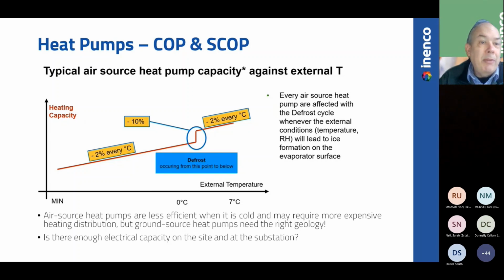The big issue with heat pumps is that air source heat pumps are less efficient and have less capacity when it's cold, and they require a defrost cycle, which may mean they need thermal buffers. Ground source heat pumps are much better, but they rely on the underground geology being suitable - you need flowing water or other permeability conditions, and we think very few sites have that. Heat pumps also tend to produce water at about 45-50 Celsius, meaning you need new radiators and pipes, and these are pretty expensive options.